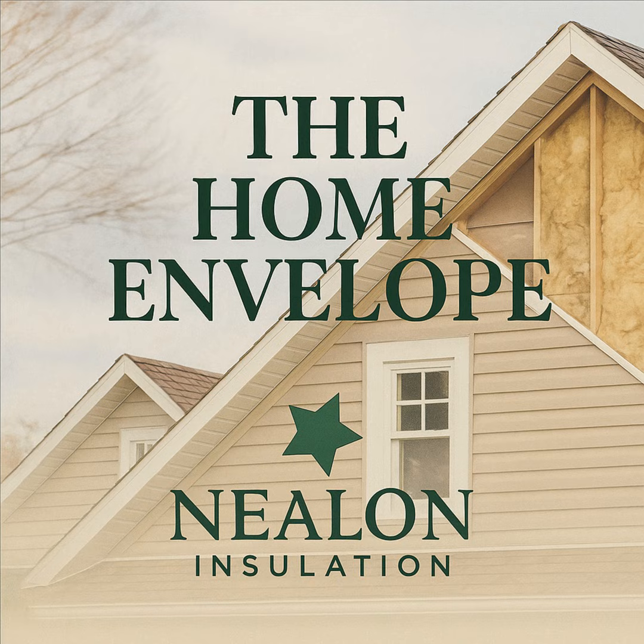That is wild. It really comes down to a concept called the neutral pressure plane. Neutral pressure plane. Yeah. It's the horizontal axis in your house where the indoor pressure perfectly matches the outdoor pressure. Okay, I follow. Below this plane, air is sucking in. Above it, air is leaking out. So it's basically the tipping point. Exactly. And if you aggressively seal the leaks in your basement or seal the penetrations in your ceiling, you physically shift where that neutral pressure plane sits, which alters how the entire building breathes.